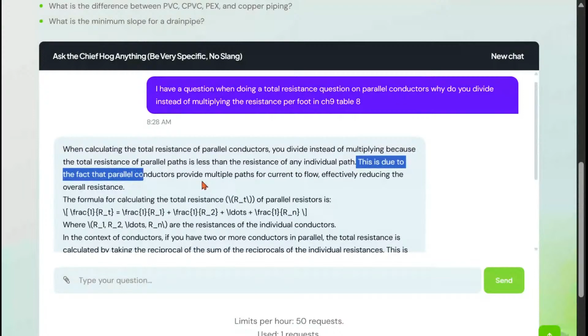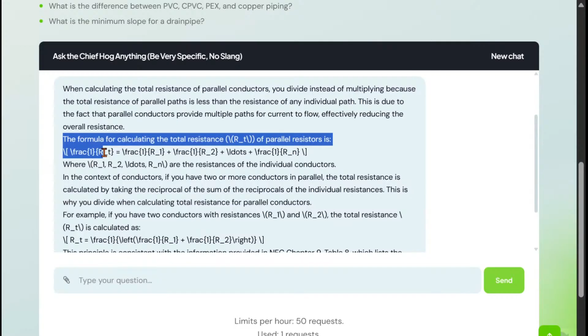When calculating total resistance of parallel conductors, you divide instead of multiplying, because the resistance of a parallel path is less than the resistance of an individual path. That's why you divide by 3 - the resistance of a single run is less when you have multiple paths. This is due to the fact that parallel conductors provide multiple paths for current to flow, effectively reducing overall resistance. This is the formula process Trade Hog uses - it brings back actual equation formulas. This principle is consistent with Chapter 9, Table 8, which lists the resistance per foot for various conductors. When using these values for parallel conductors, you apply the parallel resistance formula, and ultimately it's divided by 3.